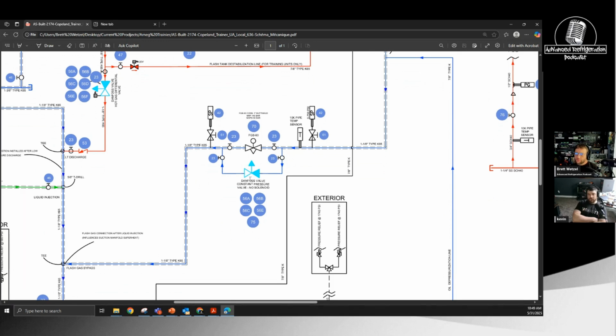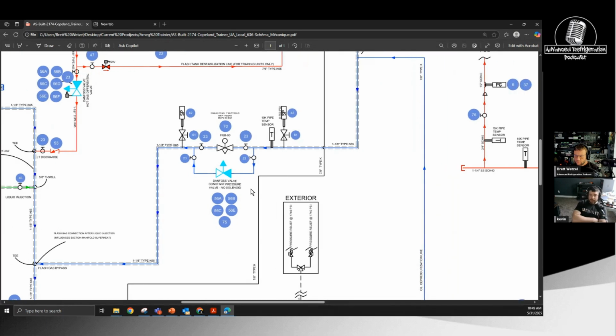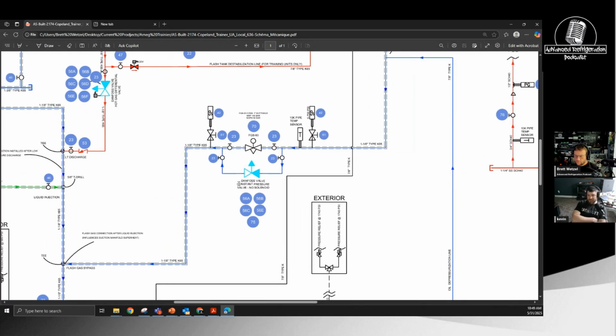So how big was this valve? Because a lot of times when they don't do these, they're the same size as this guy. It was the same size, same pipe size at least. I'm not sure, I haven't actually looked at the Danfoss nomenclature to see what cartridge is in it, but I'm telling you right now, like I had the rack at 75% loaded, and it was maintaining the flash tank beautiful in transcritical.